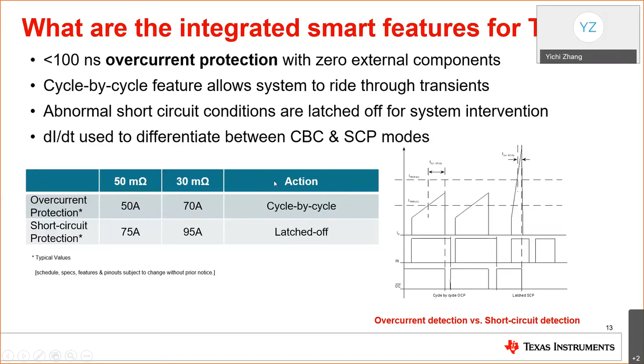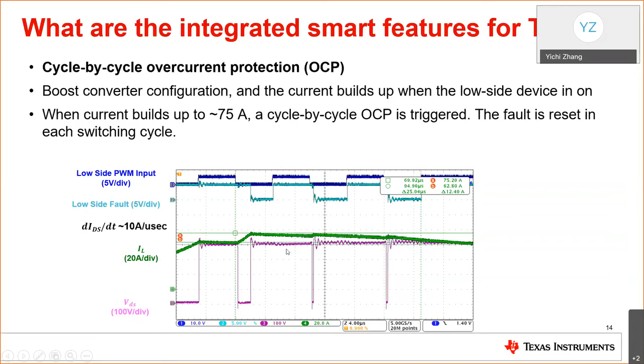So this one is a cycle-by-cycle overcurrent protection waveform that's captured on the lab bench. As you can see, whenever you have a slower di/dt, in this case it's 20 amps per division, it's rising up relatively slowly, 10 amps per microsecond, and then you will be triggering the overcurrent protection. In this case, you can see in every cycle, the device will try to start itself, and then whenever it sees it's overcurrent, then it will be shut off again. So it's a cycle-by-cycle operation, as you can see in this waveform.